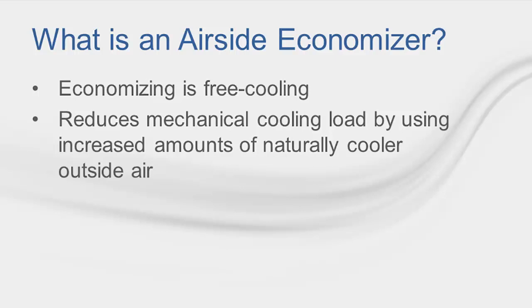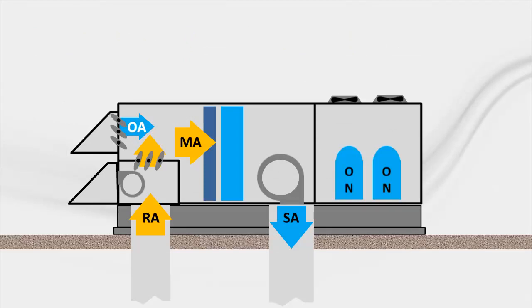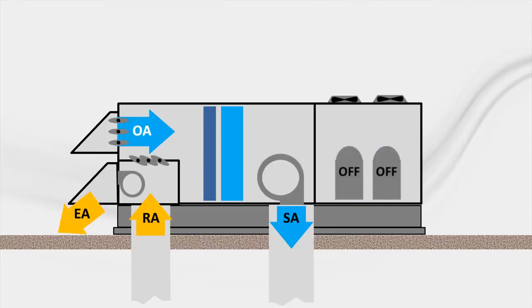Many times, the outdoor air dampers will be modulated in order to mix with the return air to deliver the proper temperature to a space. This could also mean that, if the conditions warrant, the amount of ventilation air could be 100%. However, if the outdoor air conditions do not allow for free cooling to be advantageous, the economizer cycle will be disabled and only mechanical cooling will be used to condition the space. Typical operation includes the use of mechanical cooling while bringing in minimum outside air quantities, but when the conditions are right, this outdoor air damper opens further to bring in more outdoor air, reducing the need to operate compressors to provide cooling.